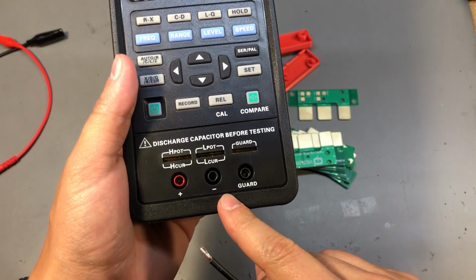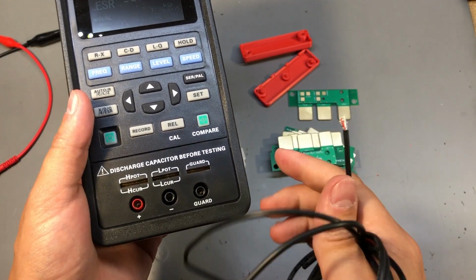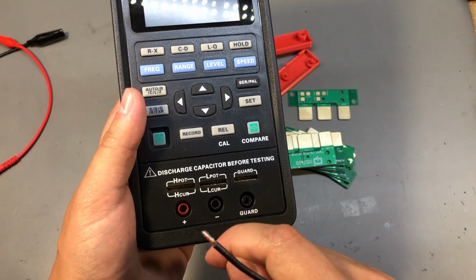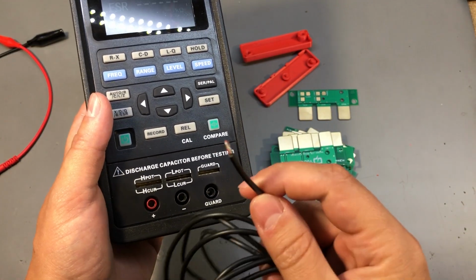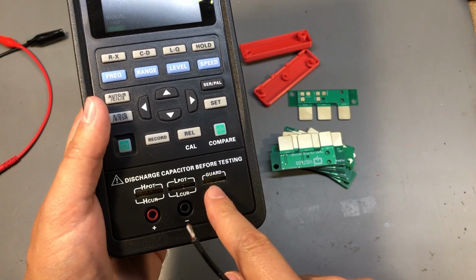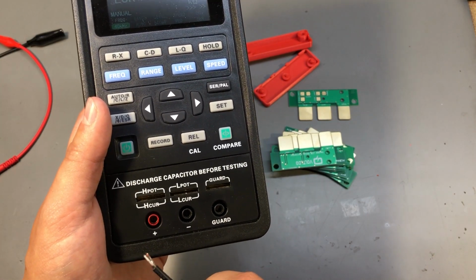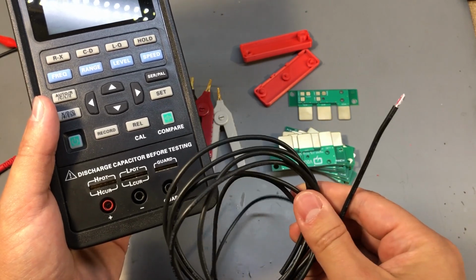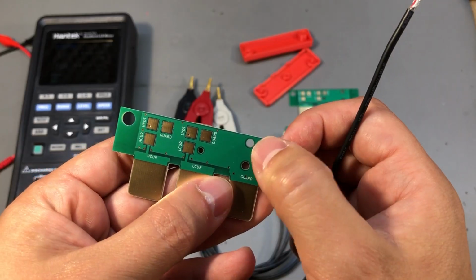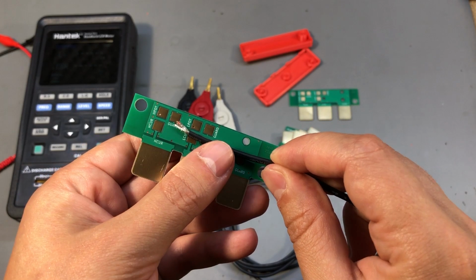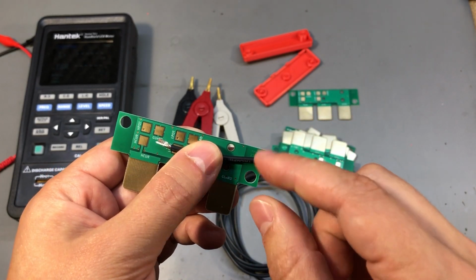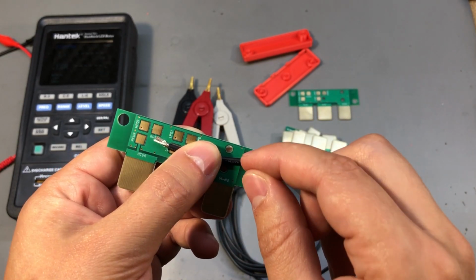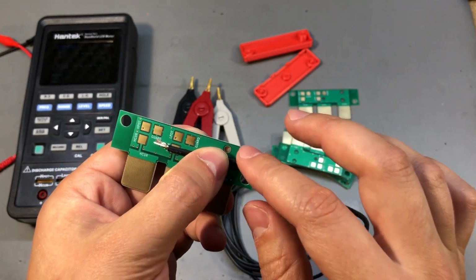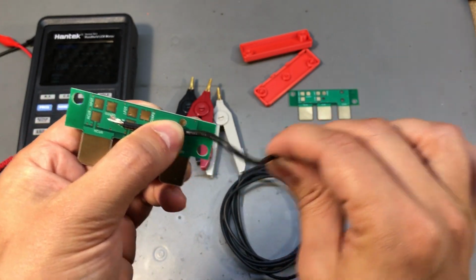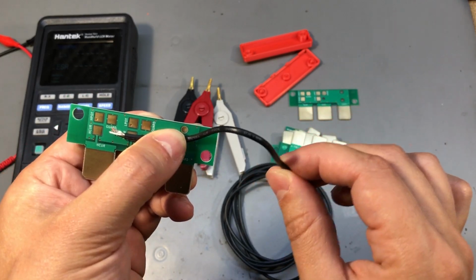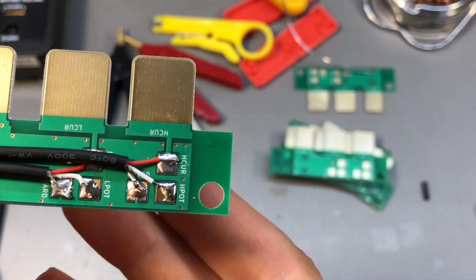The connection to the probes should be done like this: force plus and force minus inside the same shield, which is then connected to guard; sense plus and sense minus inside the same shield, which is also connected to guard. These two holes on the PCB are in here so that you can run a very thin zip tie to secure the wires to the PCB once they're soldered in. This way they will be very rigid mechanically and will not break the solder connection if stress is applied from the outside.